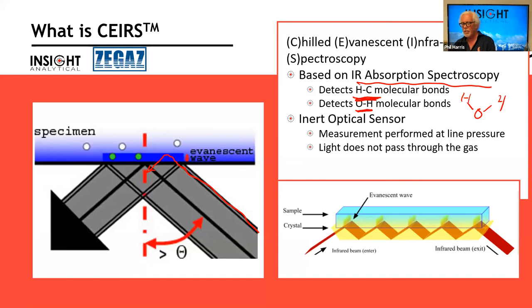So if there's just natural gas there, if there's no liquids there, the wave just goes out, touches the natural gas and comes right back in. If there's liquids there, that wave that got out of the crystal gets to interact with that liquid. So this is where the infrared spectroscopy comes in. We use how the light interacts with the liquid to determine what liquid it is. If you're familiar with infrared spectroscopy, you'll hear things called ATR cells, commonly used for liquids, attenuated total reflectance. It's an evanescent wave-based device.